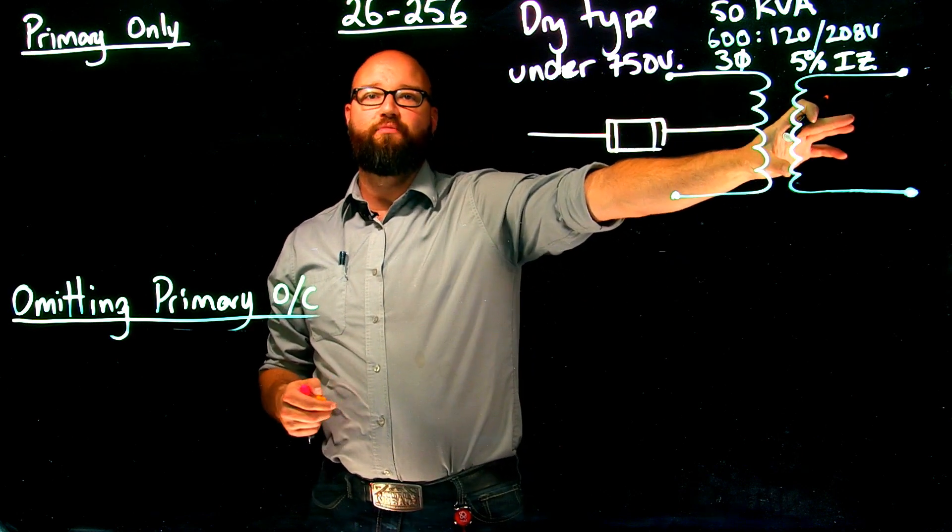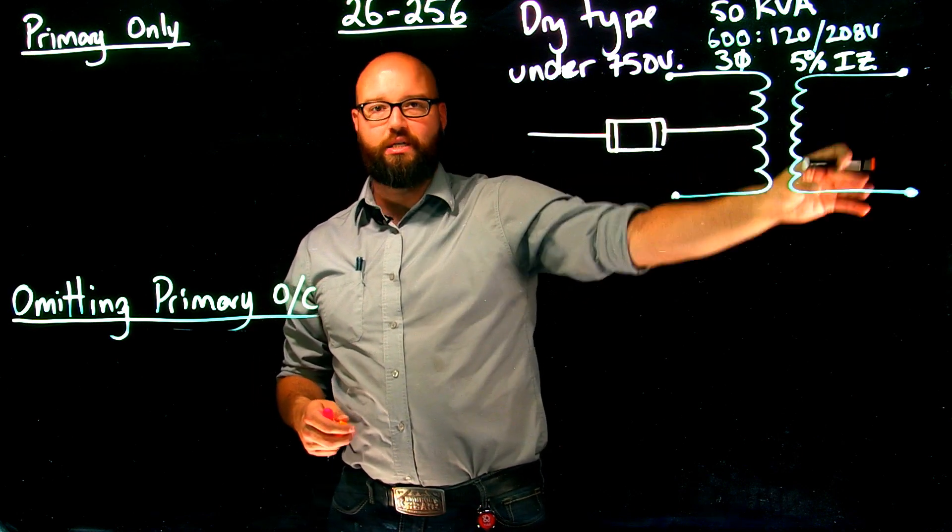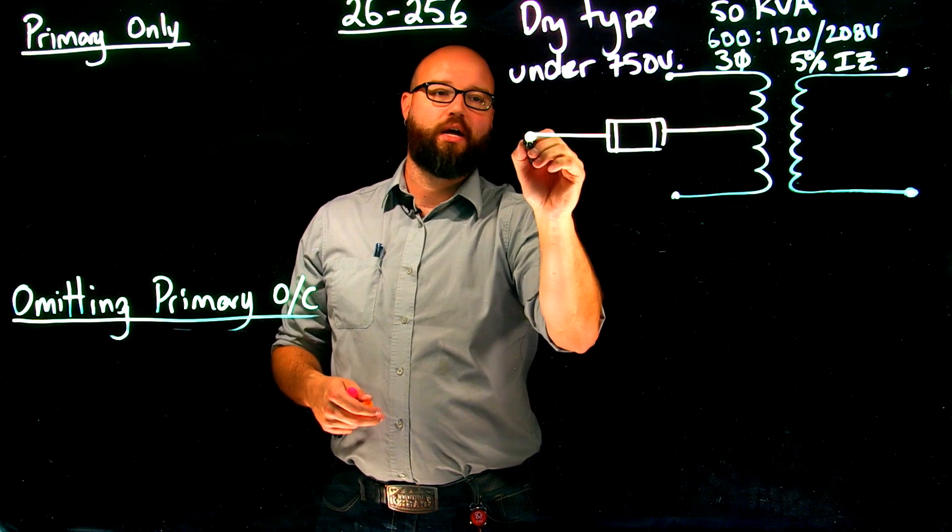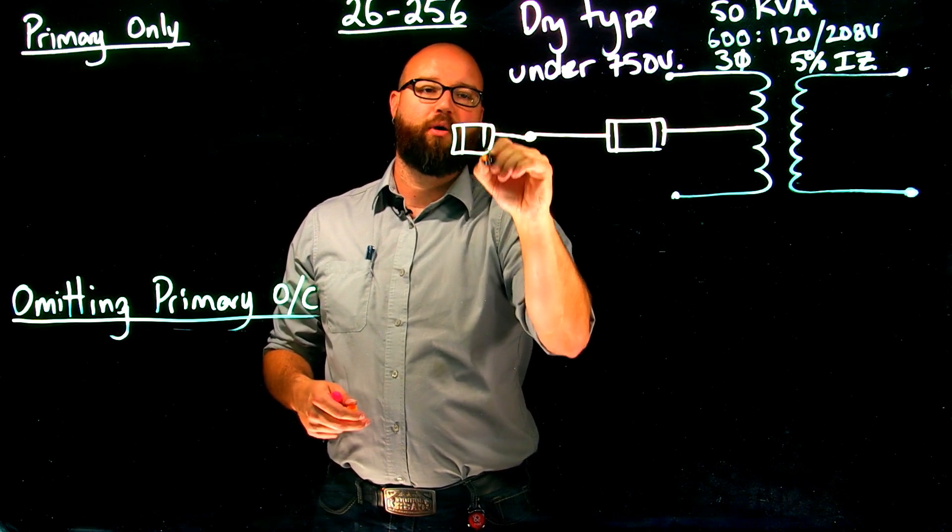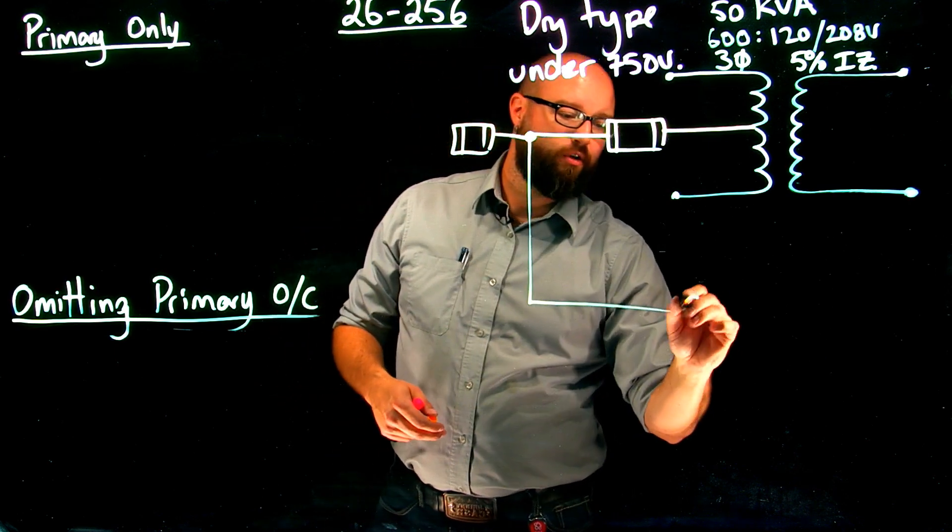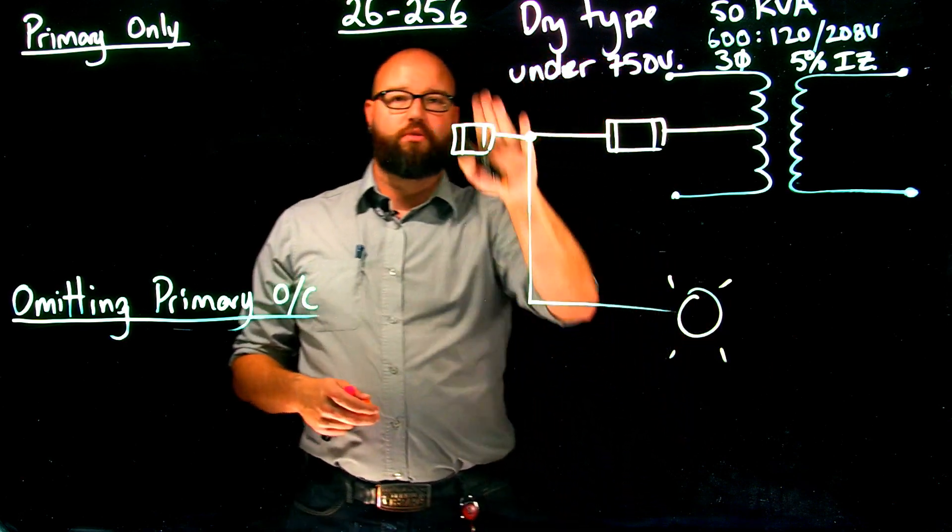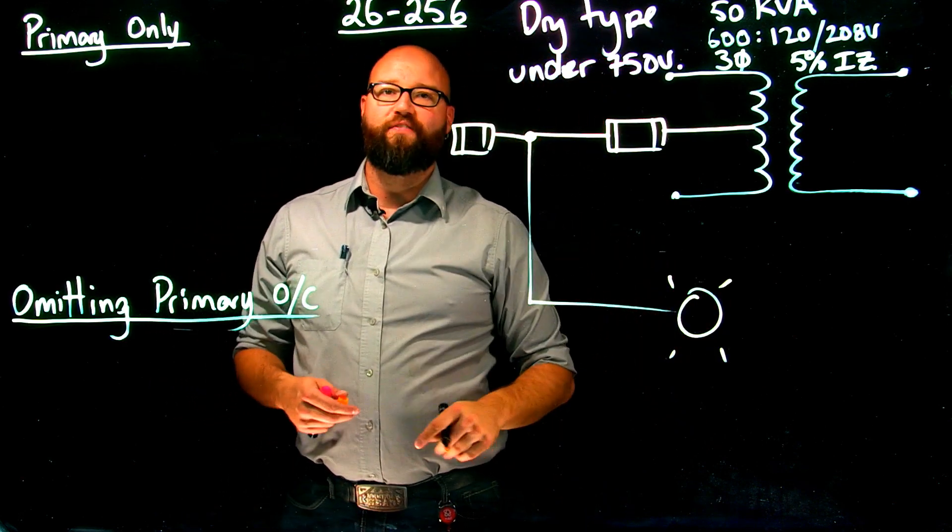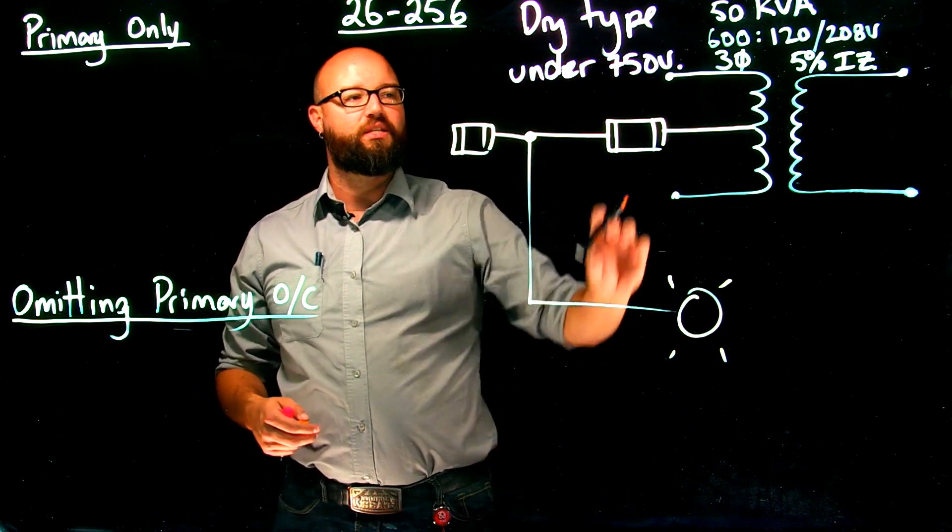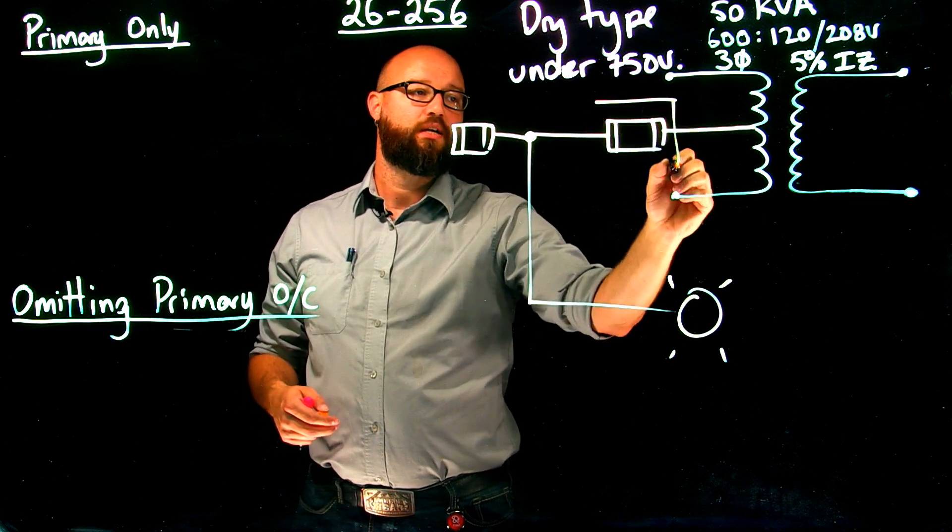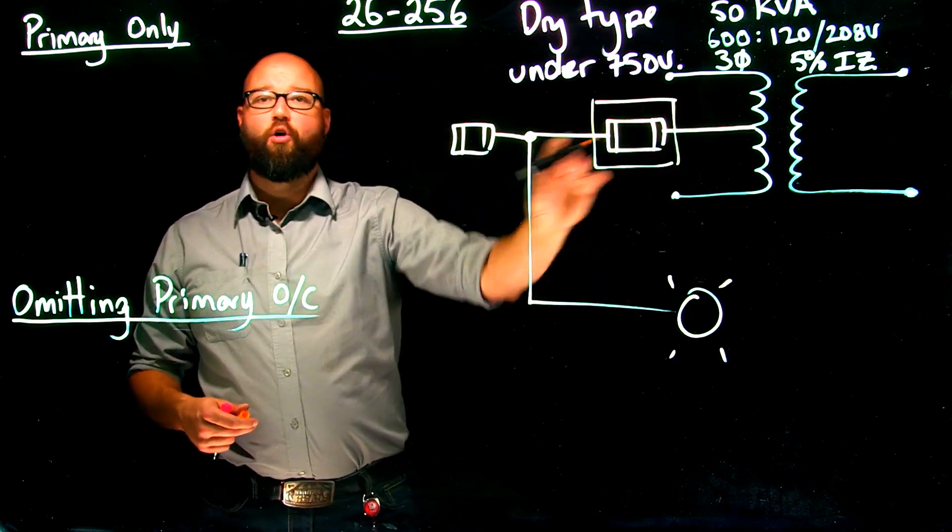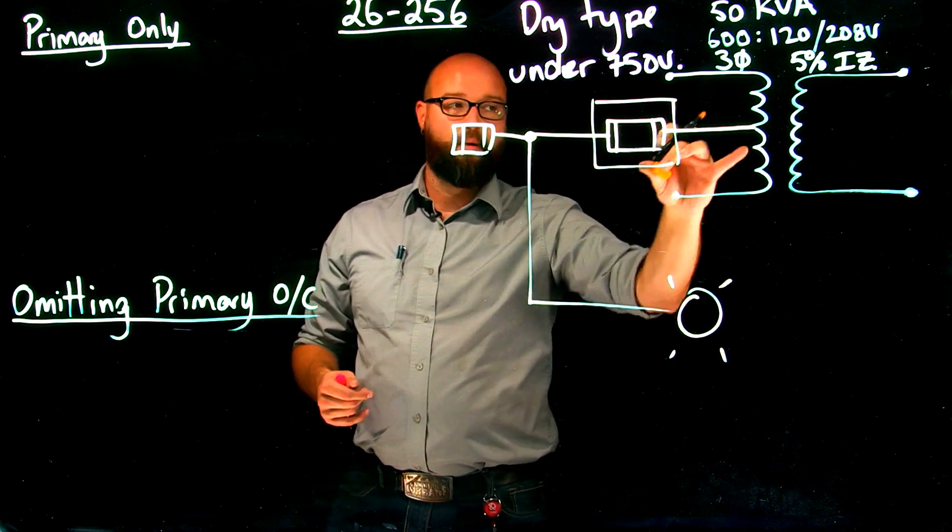versus our primary feeder, which we'll deal with when we decide to omit that primary overcurrent. So in this scenario, we have primary protection only, which adequately protects the secondary of my transformer, meaning I do not need a secondary protection in there. This could be going out to our primary feeder. We don't care right now about sizing our primary feeder; that would be done separately from this.